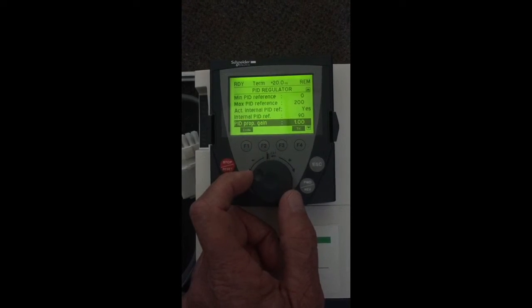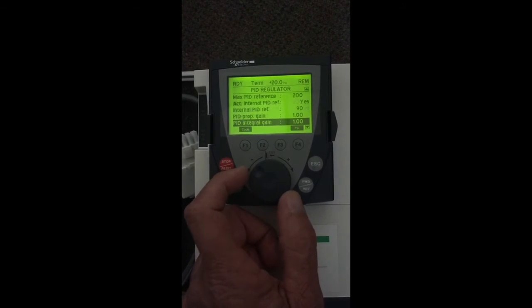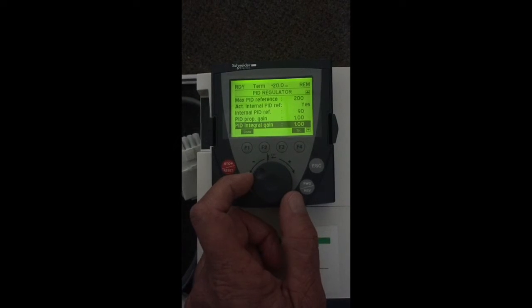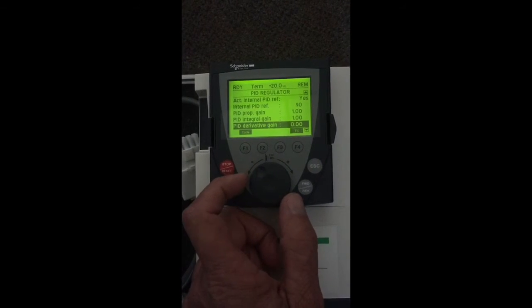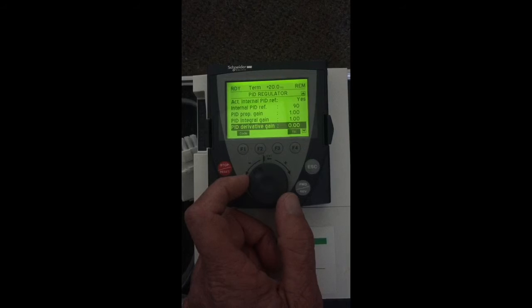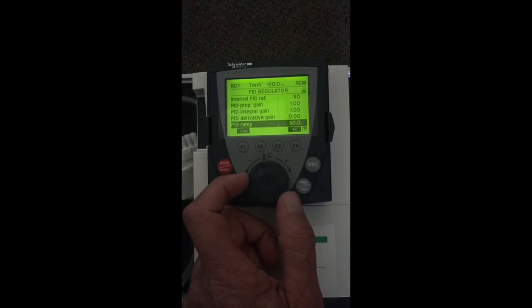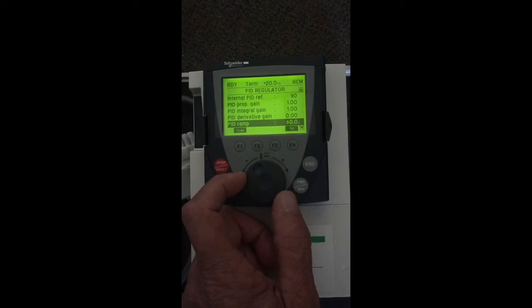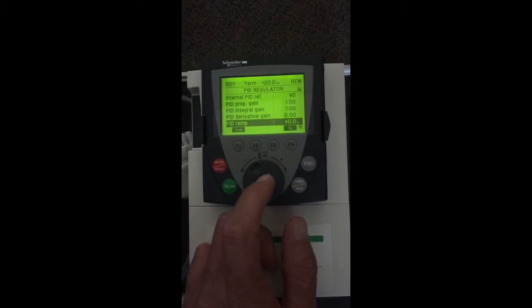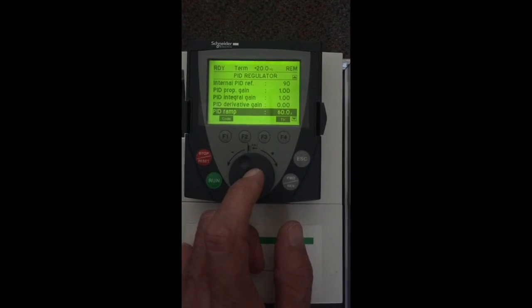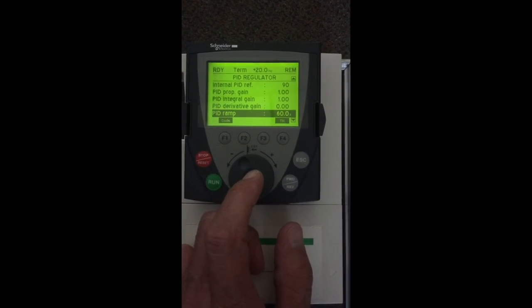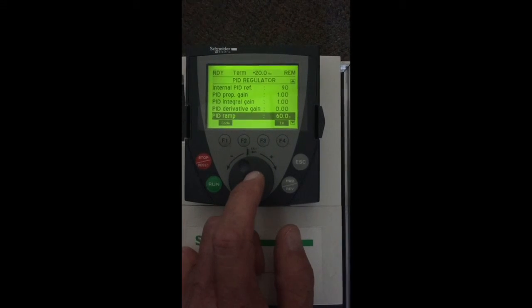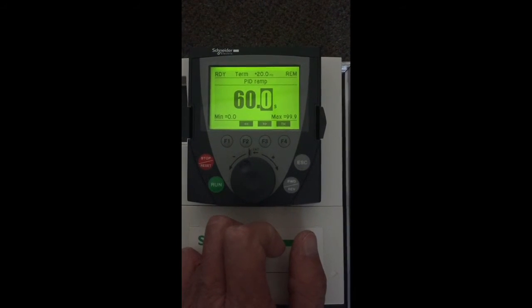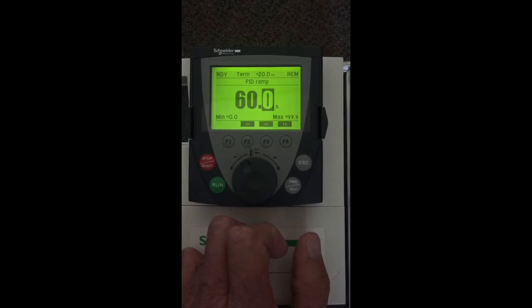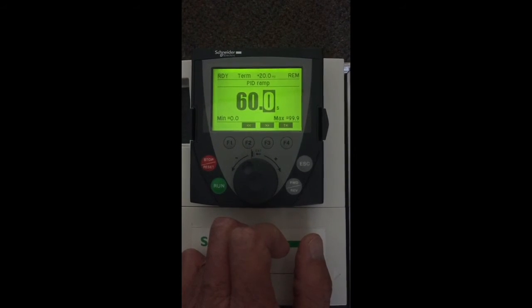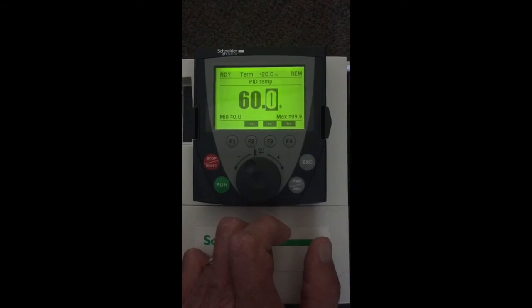I'm not changing the PID gain. I'm leaving what the drive came with. Settings, these should be okay. PID ramp time is in seconds. So how quick you want it to respond, this can be changed. You'll see the minimum 0, the maximum is 99, adjustable in between those two.